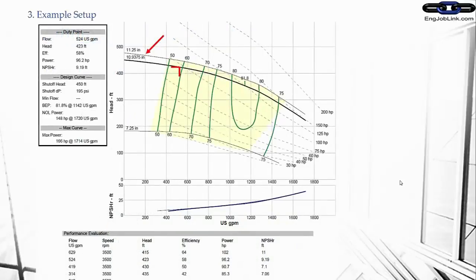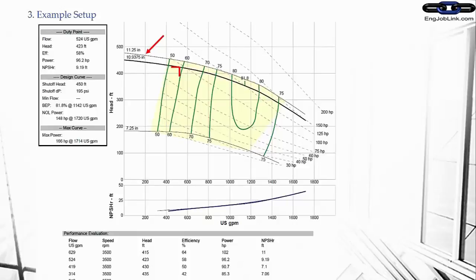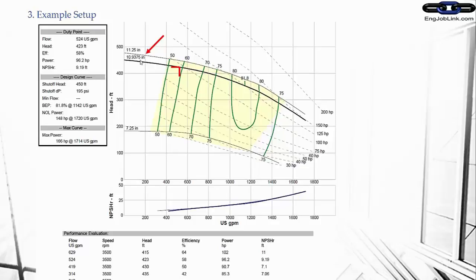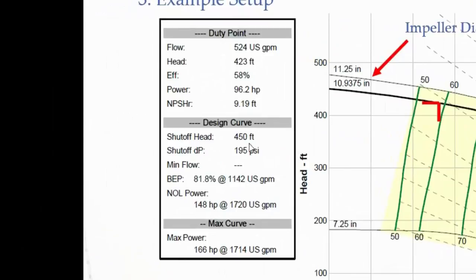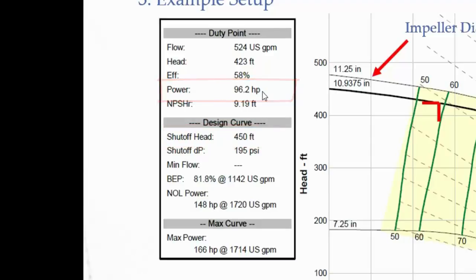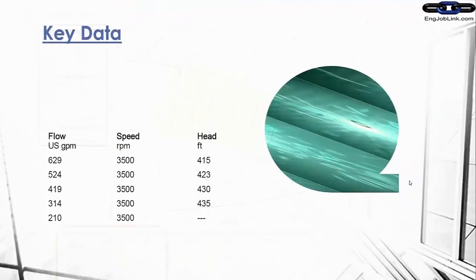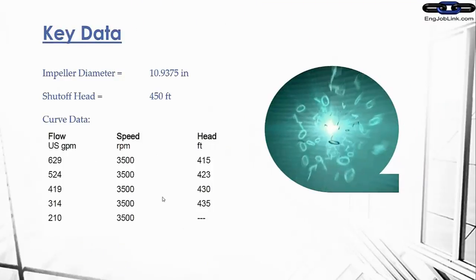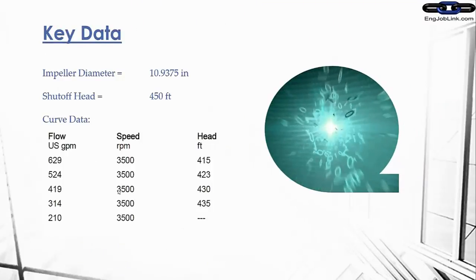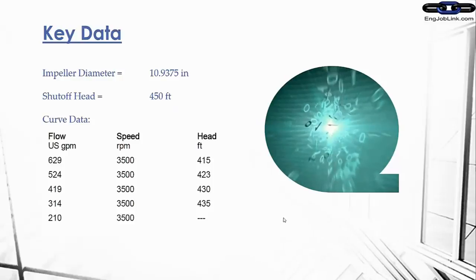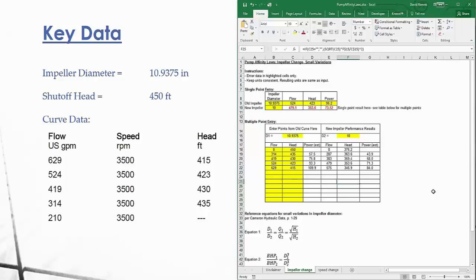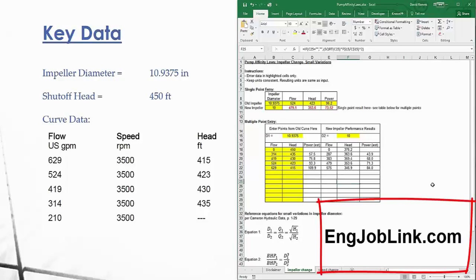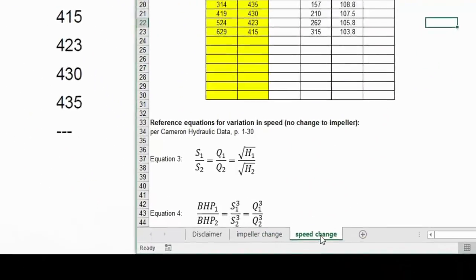What we have here is a pump curve, and this is actually a pump curve from a previous quick tip on the fire monitor. Basically, there's a lot of information here, but what we really want to focus on is this impeller diameter, 10.9375. We also want to focus on the pump curve data points and the shutoff head right here, 450 feet, and also the power, 96.2 horsepower. Here's the key data: impeller diameter, shutoff head, and curve data. Power is not on there but I'm going to discuss that in just a second. What I wanted to do here is pop up this spreadsheet, which is the free download. Basically, you've got a couple of different tabs: impeller change and speed change.